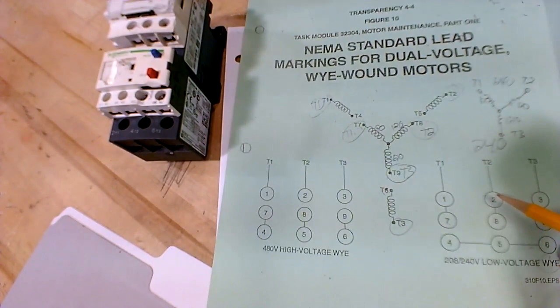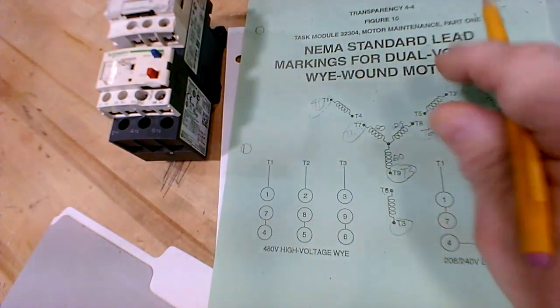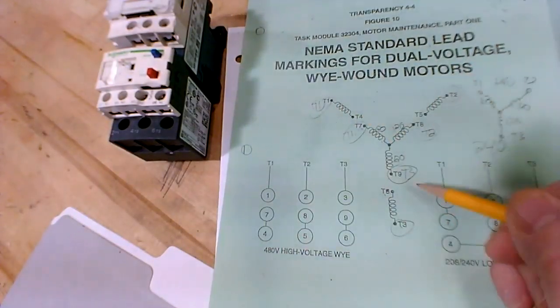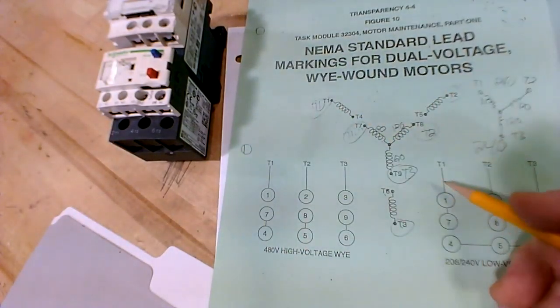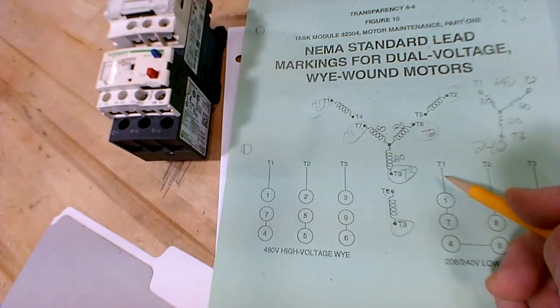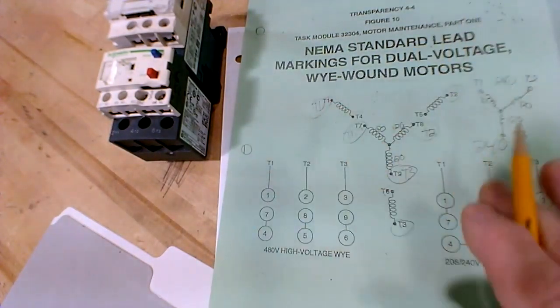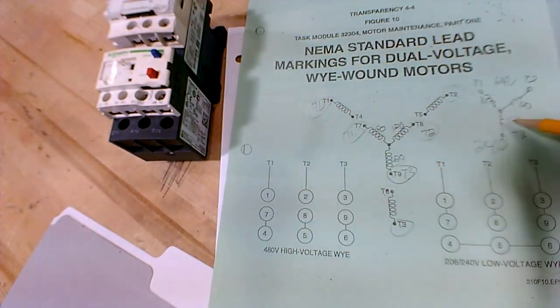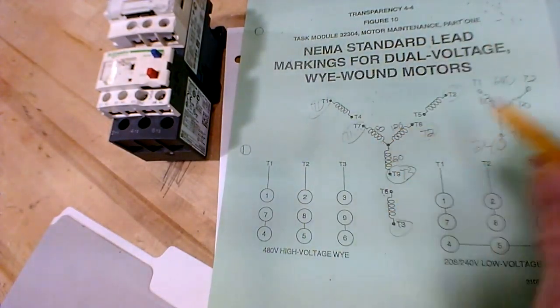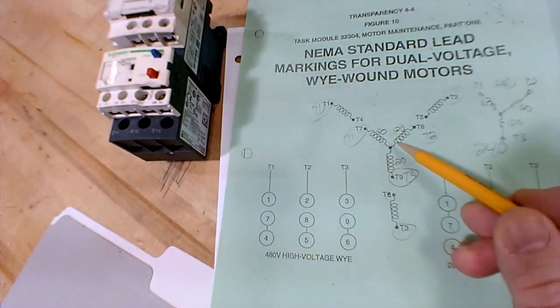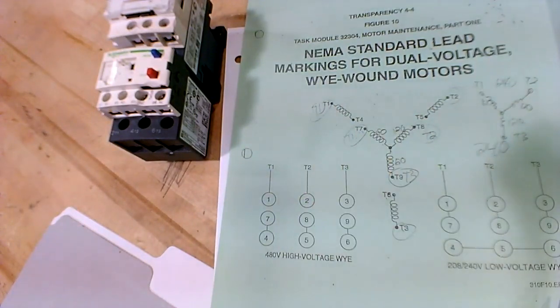And in series, I get 2 here, and they still get 120 apiece. And so the difference is, in both cases, whether you're doing low voltage or high voltage, each winding still gets the same amount of voltage, so it puts out the same amount of torque and the same horsepower and all that stuff. You get the same horsepower no matter how you do it, because you have reconfigured going from a double Y parallel to a single Y series in high voltage. And it's all a matter of going series parallel internal to the motor. And that's why it works the way it does.